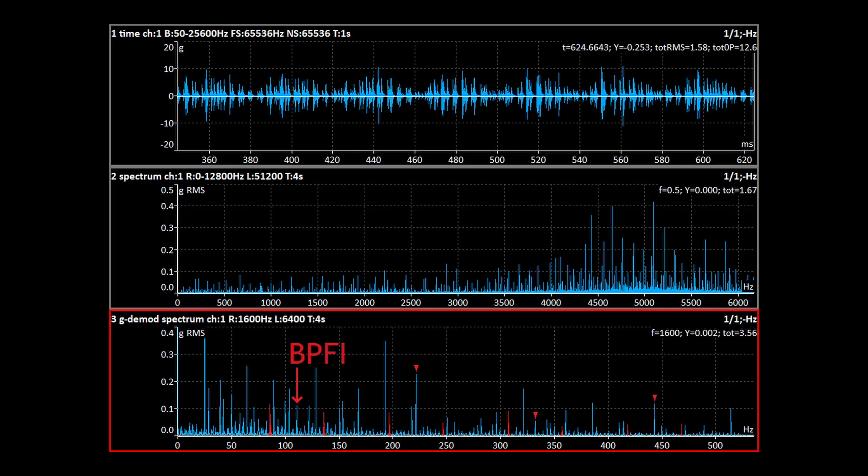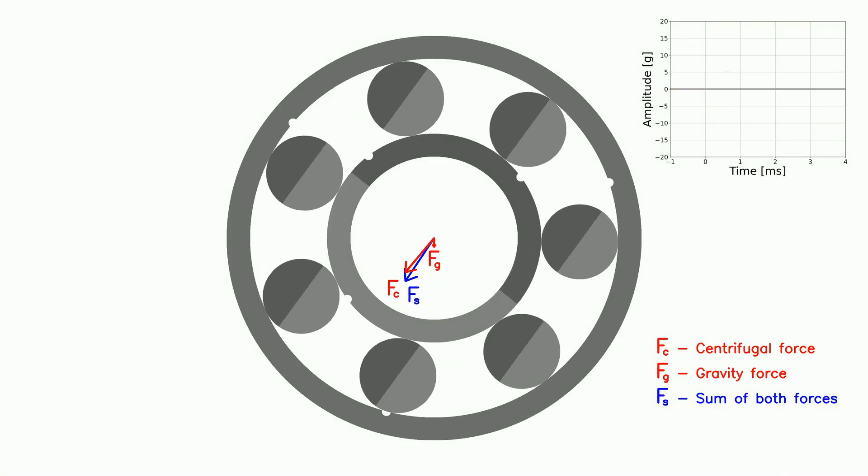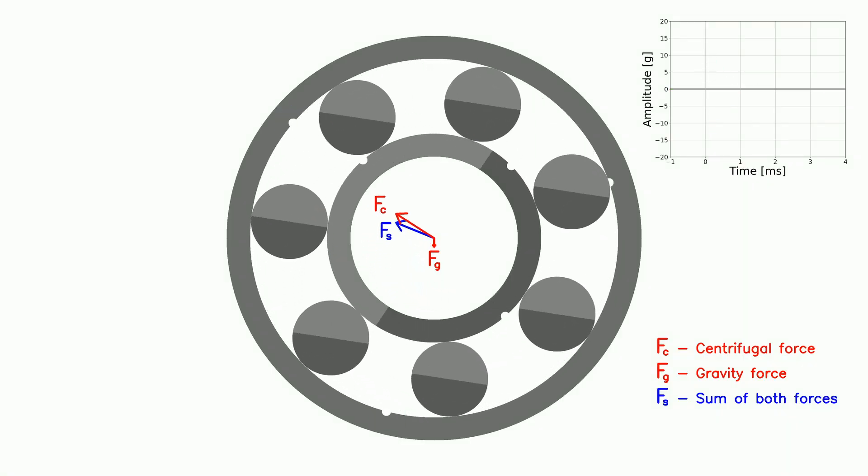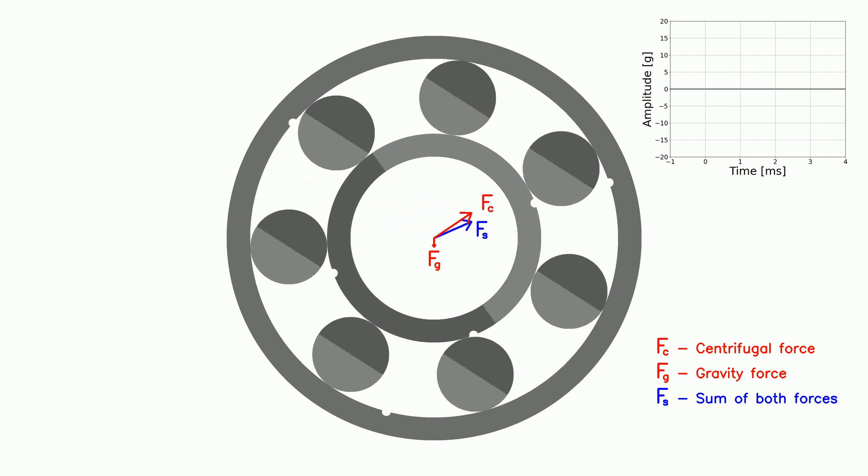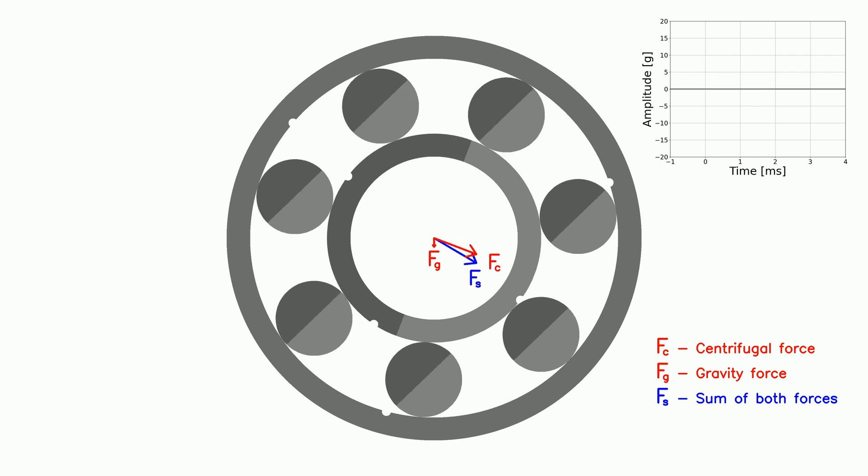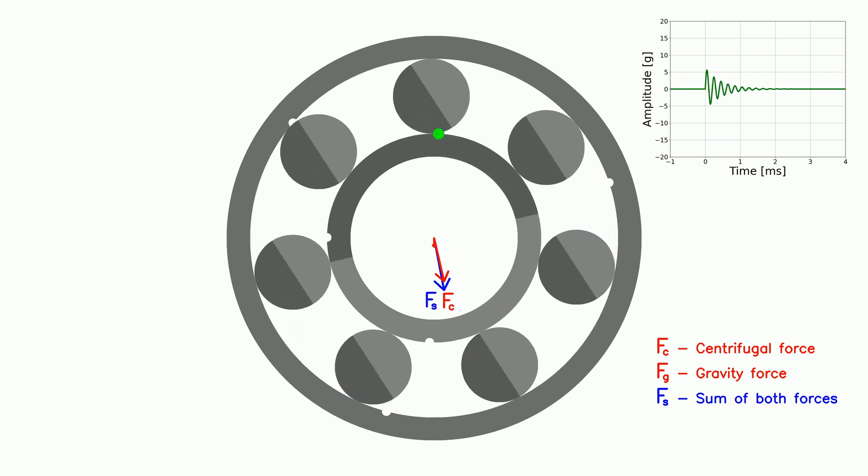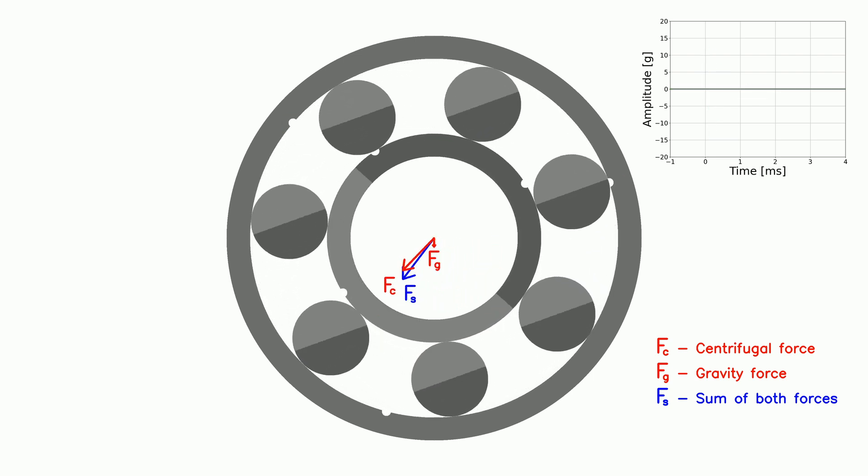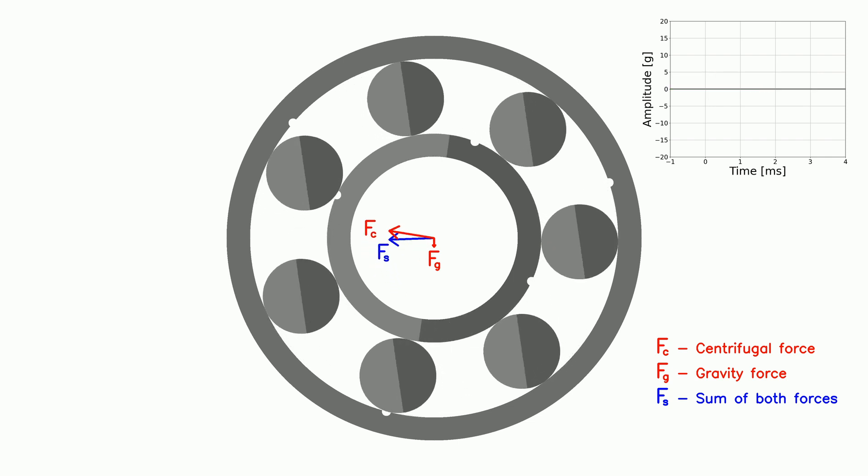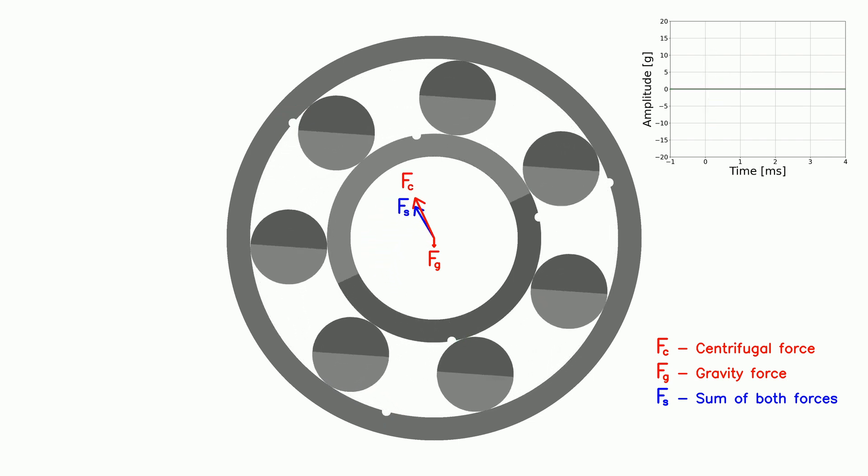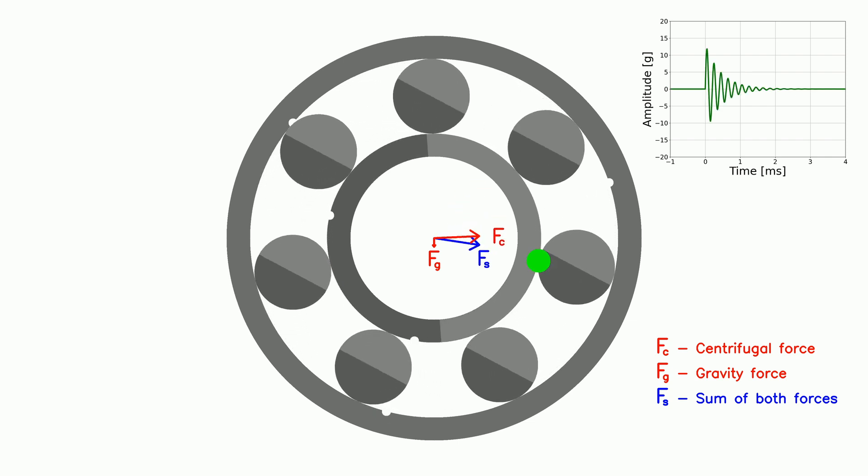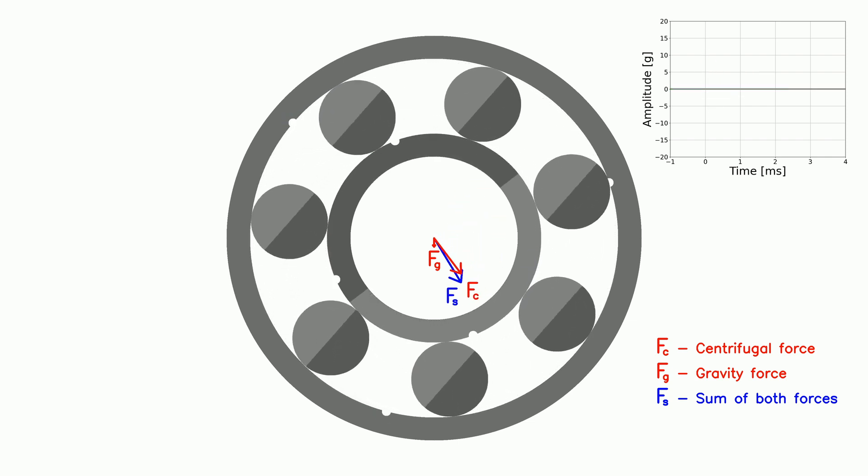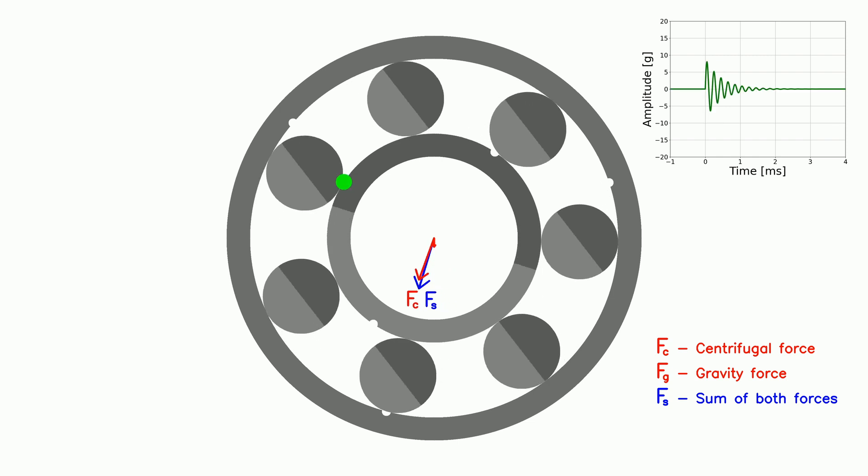We must note that this almost never happens. The centrifugal force from unbalance is usually much larger than the downward force of gravity. When examining bearing faults, unbalance is usually behind modulation. Effect of the shaft's weight is negligible compared to the effect of unbalance.